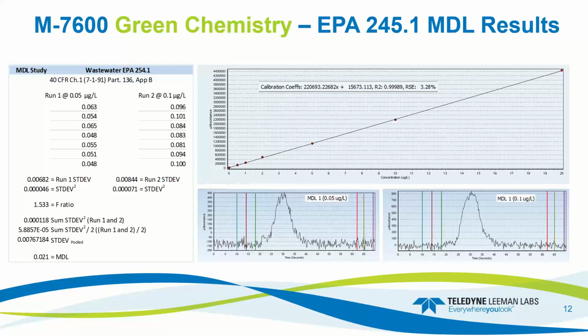So my first step was to run an MDL study using 245.1 sample preparation and the green chemistry parameters that I'd optimized. So the calibration curve looks great. You can see the peak profiles at the bottom right. For my study, I used 7 replicates each of a 0.05 microgram per liter and a 0.1 microgram per liter sample. You can see the raw data on the left, and my final MDL result was 0.021 micrograms per liter, or about 21 parts per trillion.